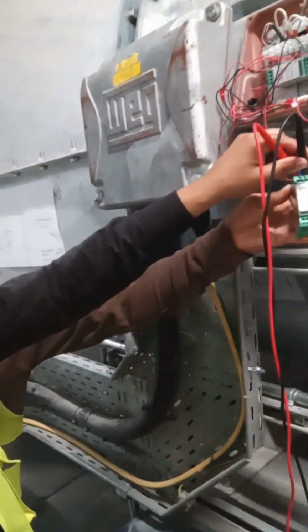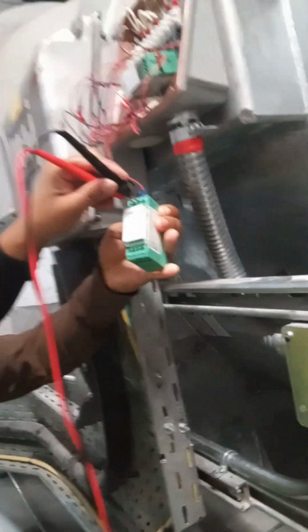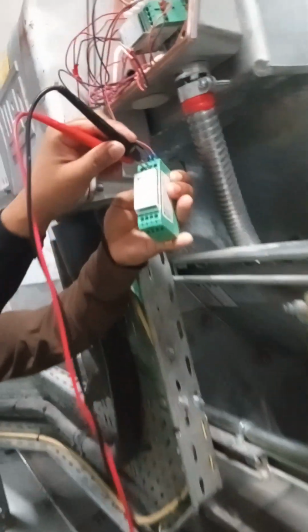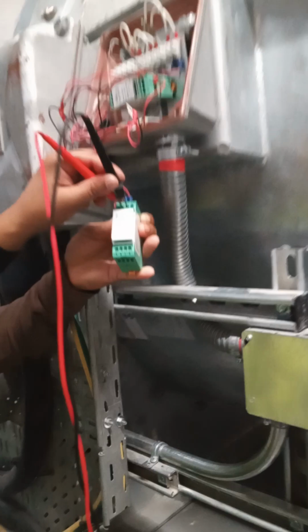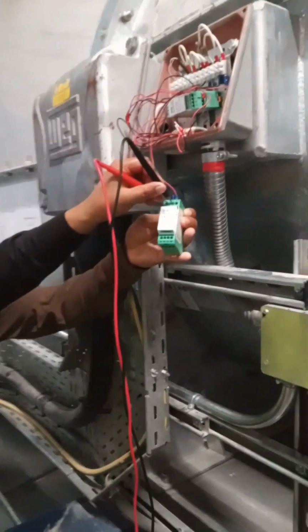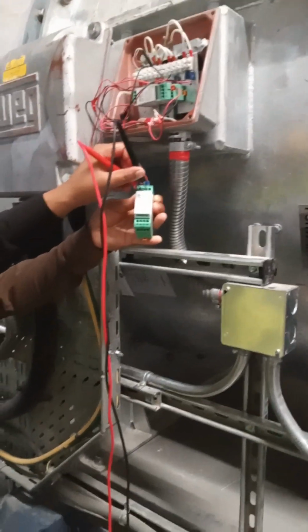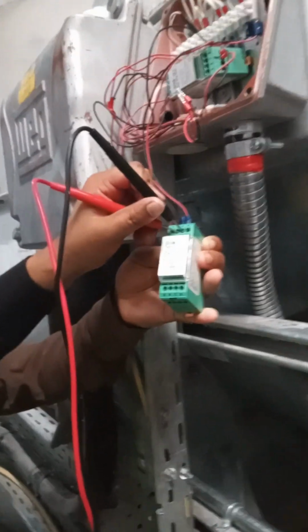When we connect the BMS cable, we get the value. If you are still not getting it, check the fuse. And even then, if not getting a value, check the connection at the AI channel, whether it is on current or not. If it is on current, then again check in the program that it is in current, its current settings, and also check the raw value and scaling. This is only okay. Thanks.